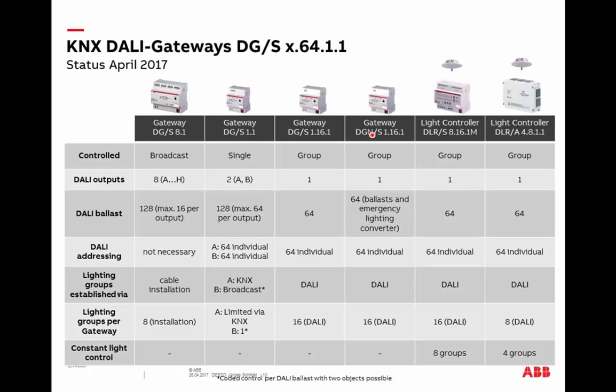The DGS 1-16-1 has one channel but allows creation of DALI groups — DALI supports up to 16 groups on the DALI side. It is easier to create DALI groups than grouping in ETS, and for projects needing up to 16 groups, this device is frequently used. The DGS 1-16-1 with emergency lighting adds integration of emergency light converters in software — converters can be connected and all necessary tests triggered via this gateway, with test results sent back for processing in a superior visualization on the KNX side.